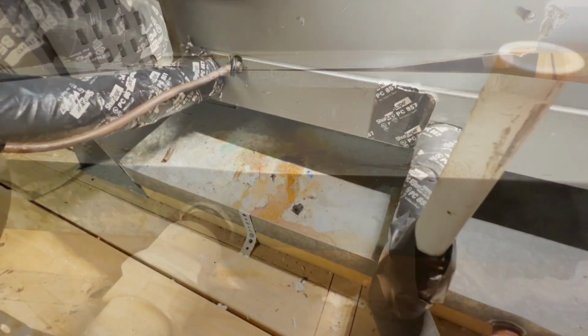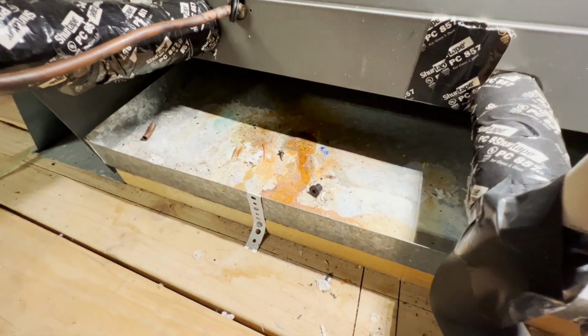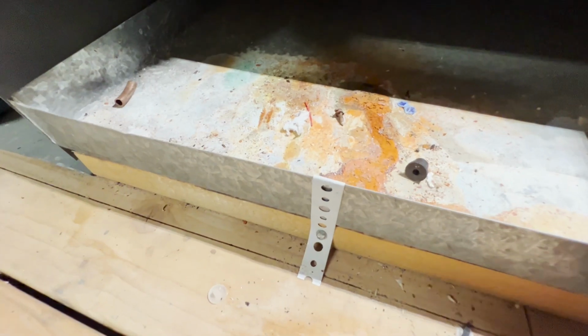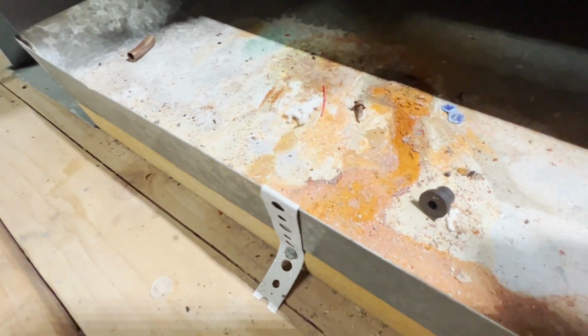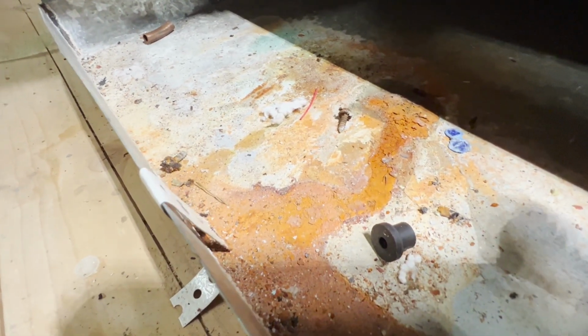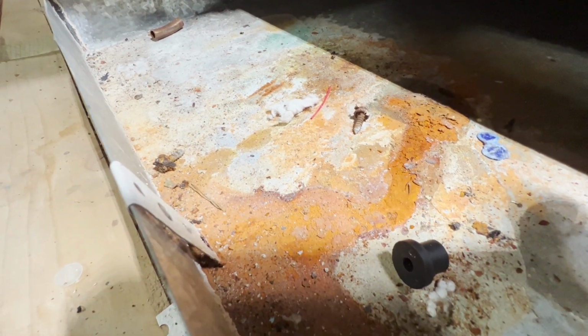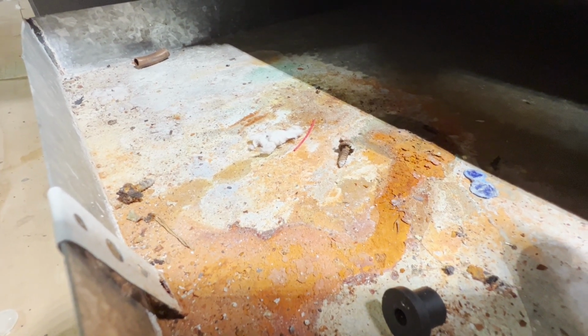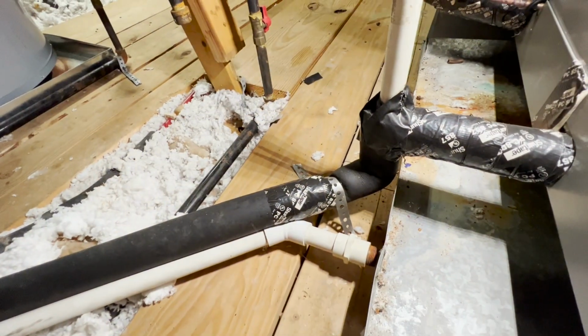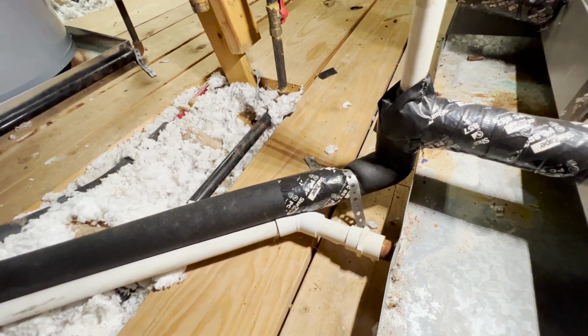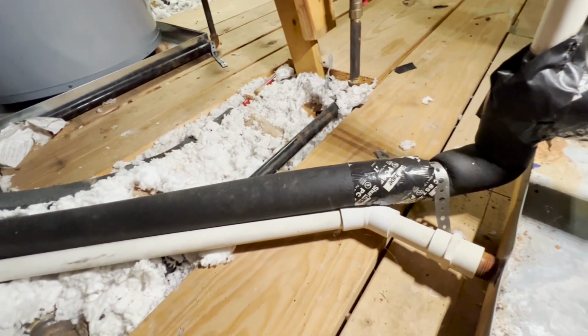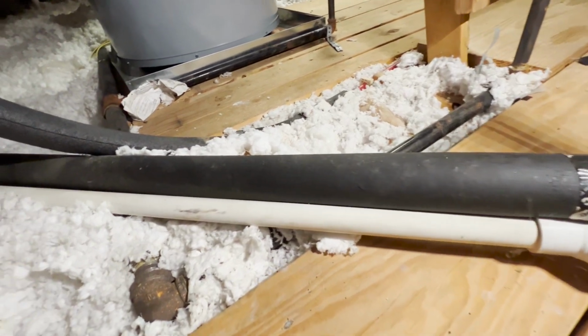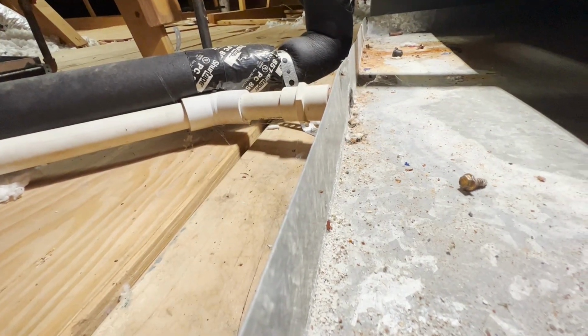Now, if you look at what's inside this drain pan, and this is representative of almost every single drain pan in Houston, you see screws, there's some insulation in there, there's a little piece of pipe in there. The AC tech who was working on this probably dropped these screws and didn't bother to pick them up. So if you get a clog in this line, this one can sometimes be a challenge to actually get that clog out because it involves stuff like insulation, which can easily clog a pipe.